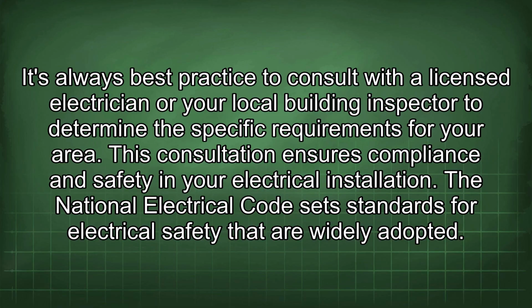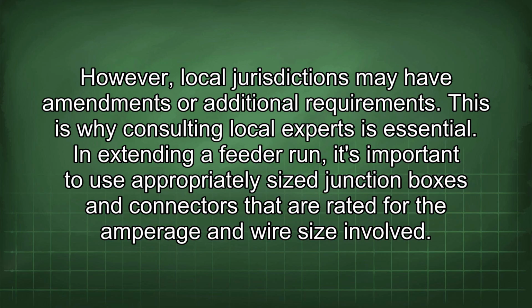The National Electrical Code sets standards for electrical safety that are widely adopted. However, local jurisdictions may have amendments or additional requirements. This is why consulting local experts is essential. In extending a feeder run, it's important to use appropriately sized junction boxes and connectors that are rated for the amperage and wire size involved.